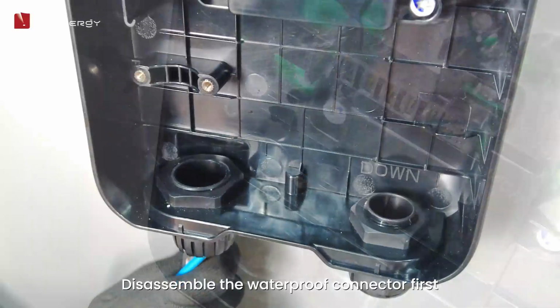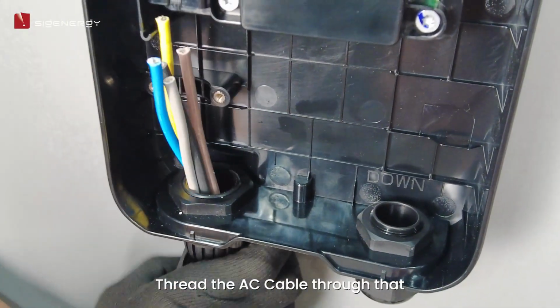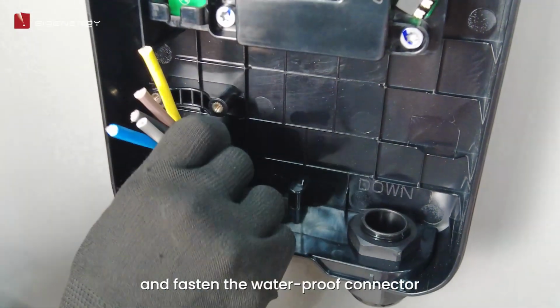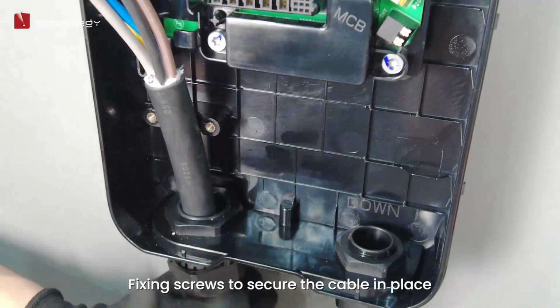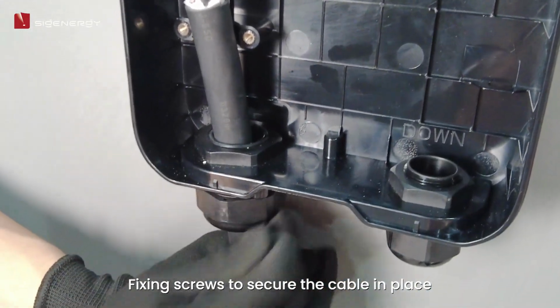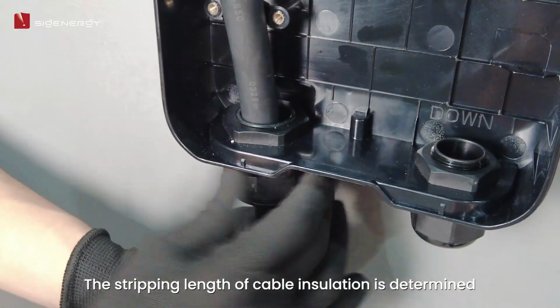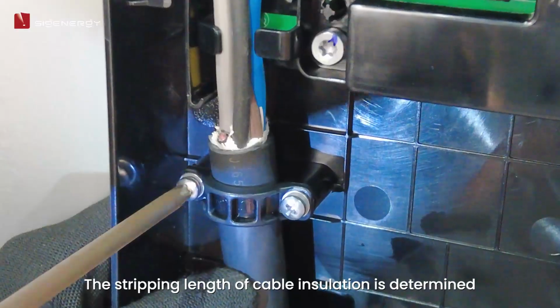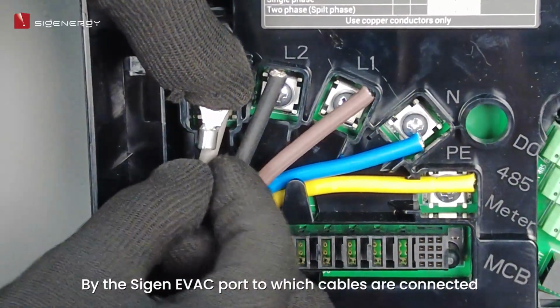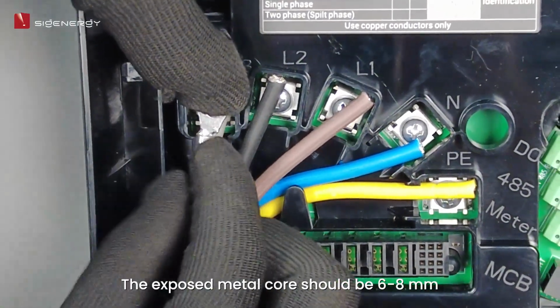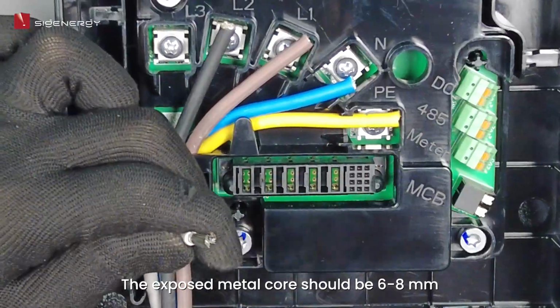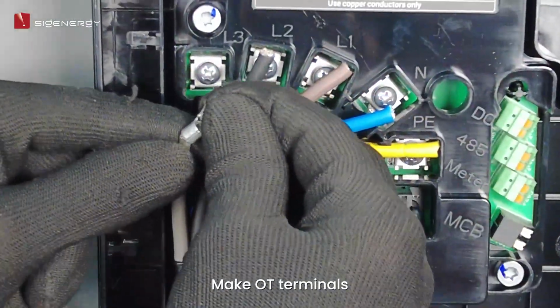Disassemble the waterproof connector first. Thread the AC cable through that and fasten the waterproof connector. Fix screws to secure the cable in place. The stripping length of cable insulation is determined by the Sigen EVAC port to which cables are connected. The exposed metal core should be 6 to 8 millimeters. Make OT terminals.